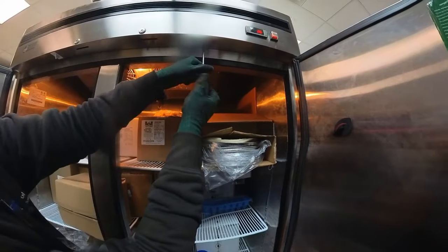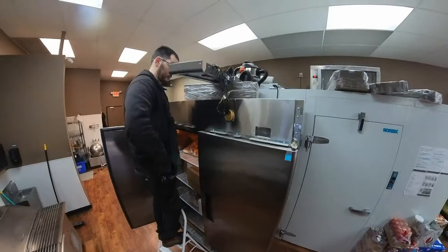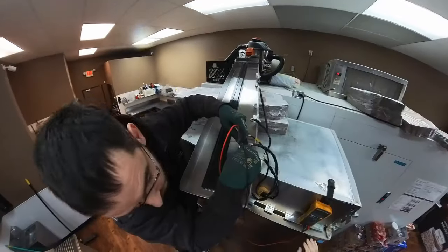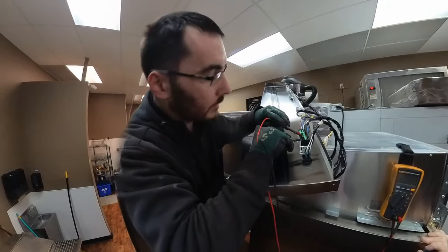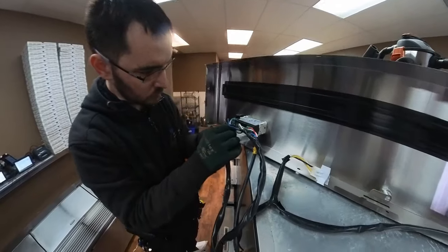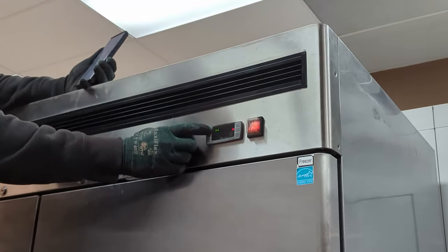He is younger than me, but he always seems to win. With the cover removed, we can access the digital controller and do some testing on it. It seemed like power was going into the controller but not coming out of it — it's not outputting from the controller. So Trevor quickly rewired it to make the fans run continuously, and we put it through a defrost cycle when we went to grab a new controller.